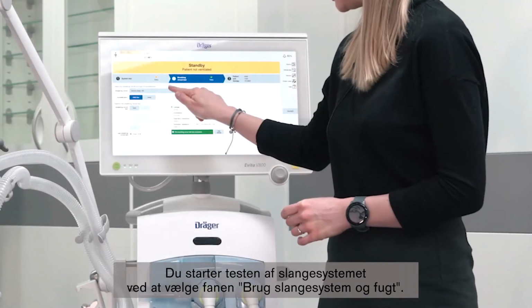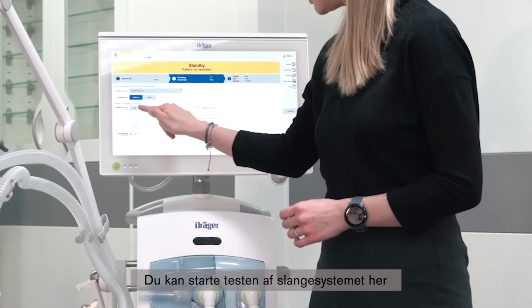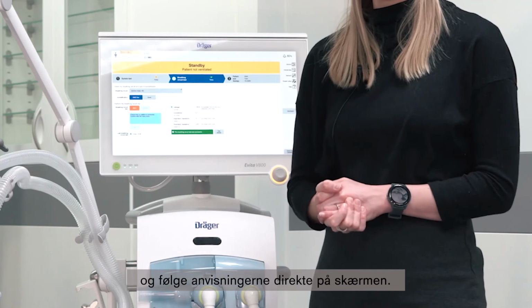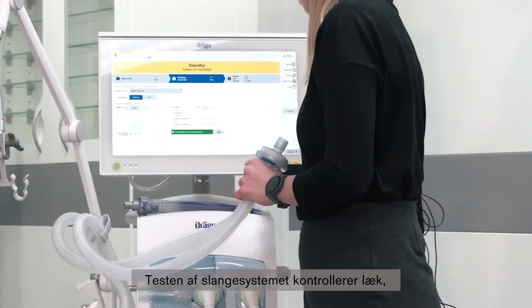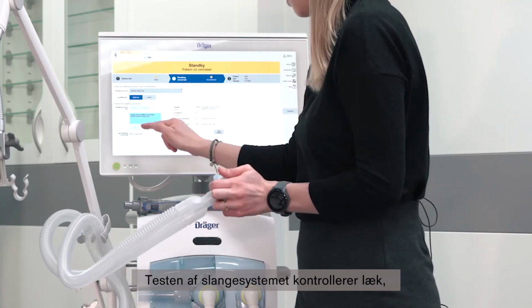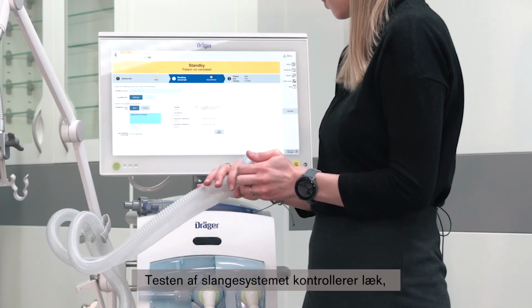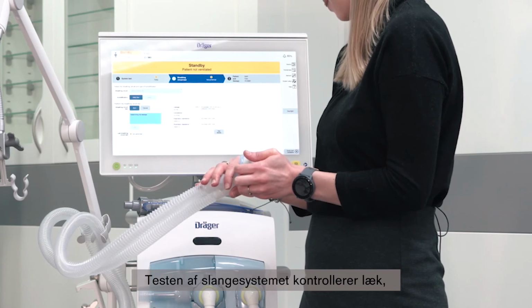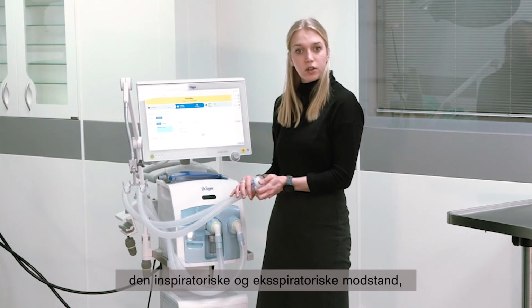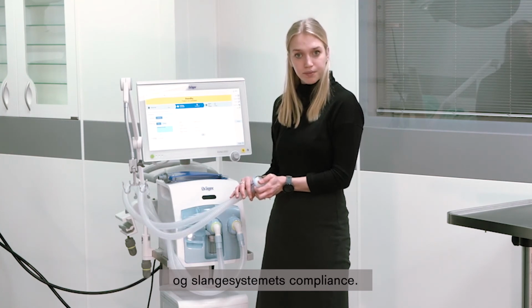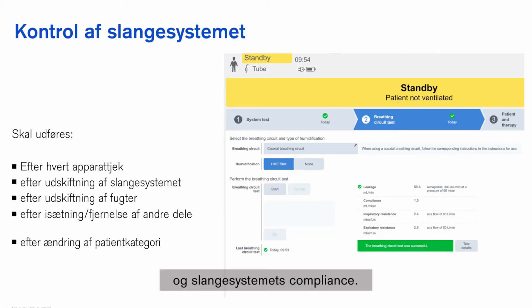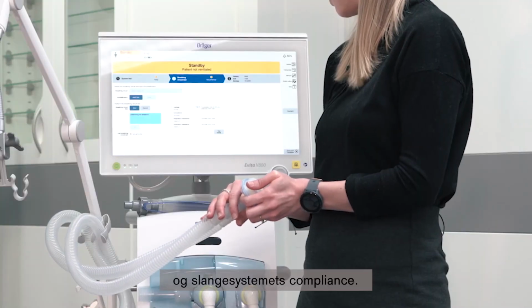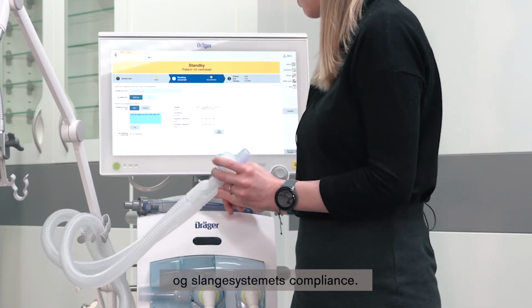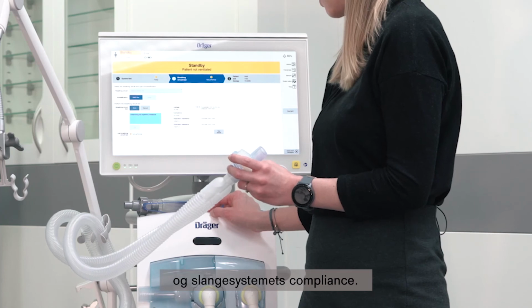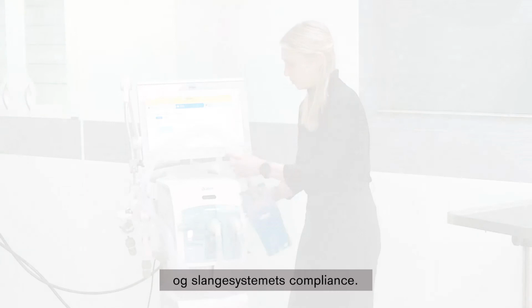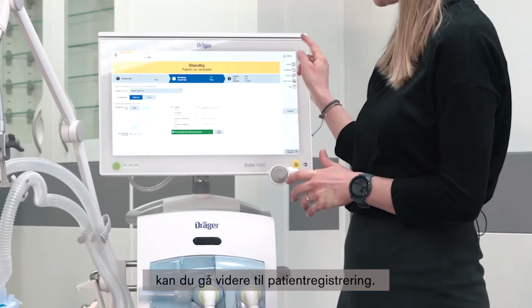To start the breathing circuit test, please select the used breathing circuit and humidification type. You can start the breathing circuit test over here and follow the instructions directly on the screen. The breathing circuit test determines the leakage, the inspiratory and expiratory resistance, and the compliance of the circuit system. After successful completion of the breathing circuit test, please continue with the patient admission.